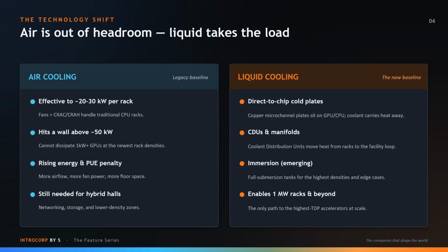The heat problem forced a technology transition, and that transition is happening in a single product cycle. This slide frames the actual technology shift. On the left, air cooling: effective to roughly 20 to 30 kilowatts per rack, still useful for networking, storage, and lower density zones. But it hits a wall above about 50 kilowatts, and every extra bit of airflow costs fan power, energy, and floor space.